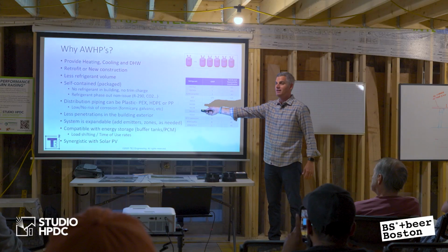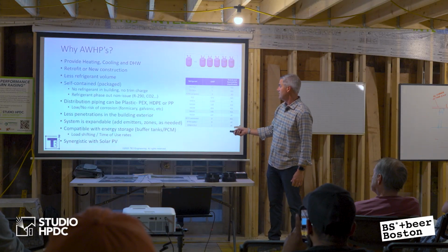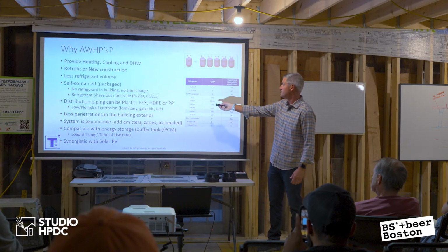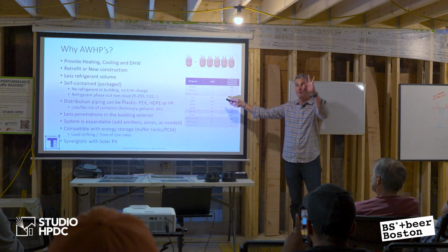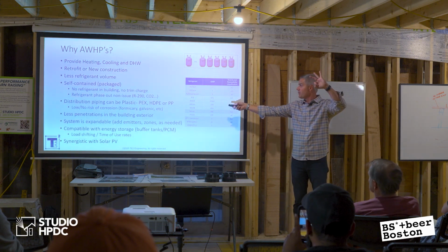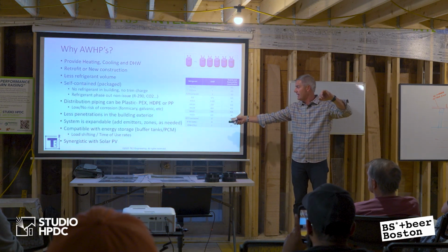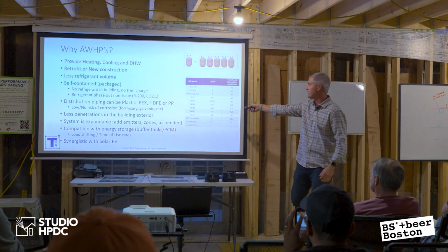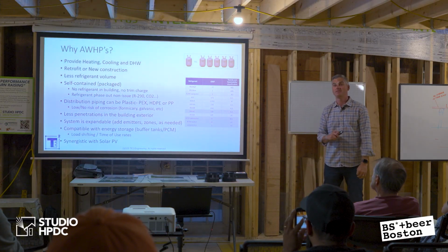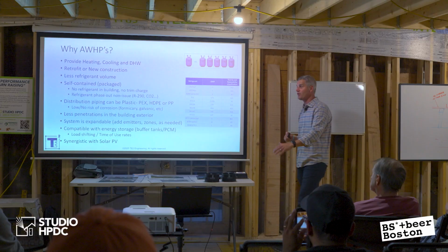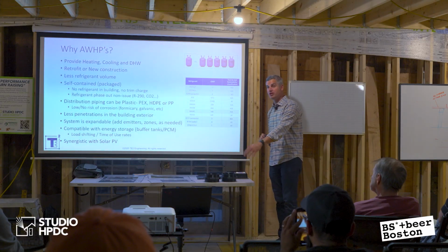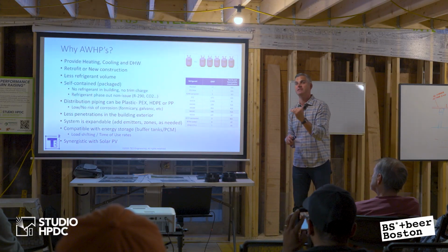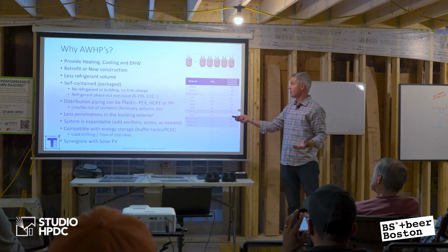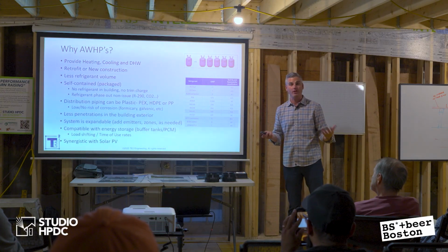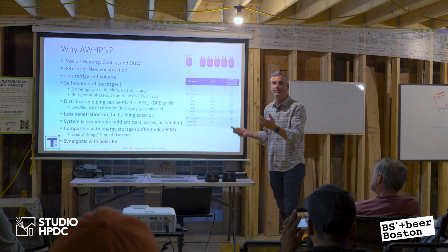The new ones that I really like that are coming from Europe, which haven't been approved yet, are R290. R290 is propane. It has a global warming potential of 3, compared to R32, which is 675, and R410A, which is 2,000. So we're going with better, natural refrigerants, lower GWPs, better efficiencies. The only downside is that R290 is propane, so everyone gets scared because it is flammable. Right? But it's outside, self-contained.